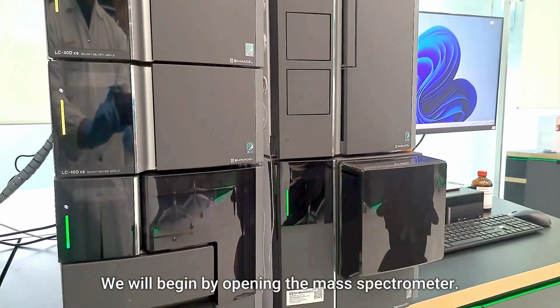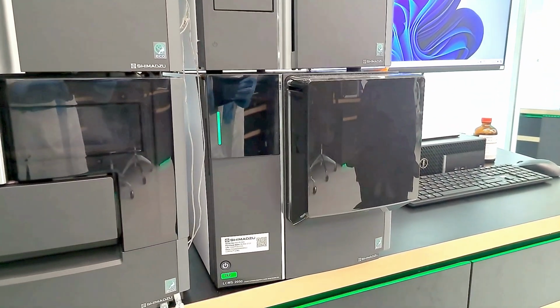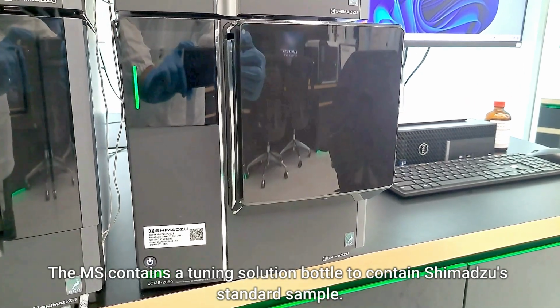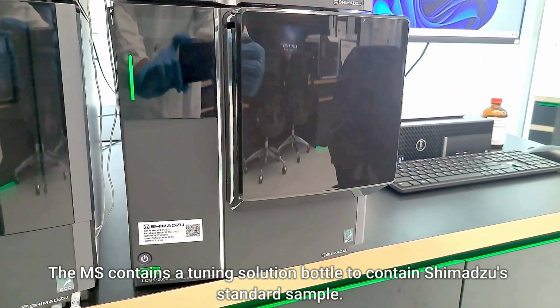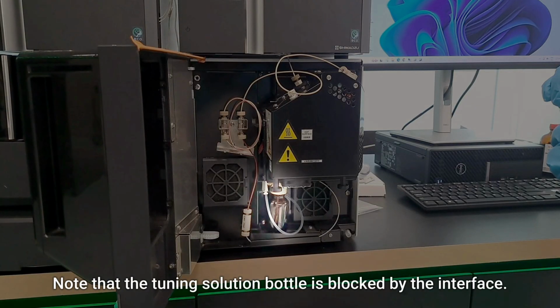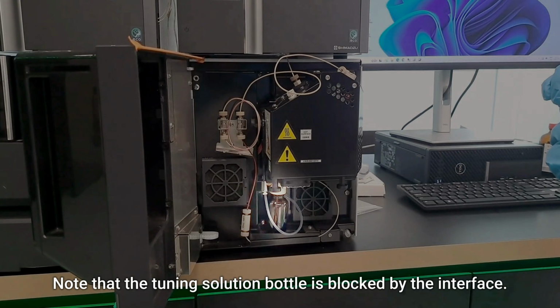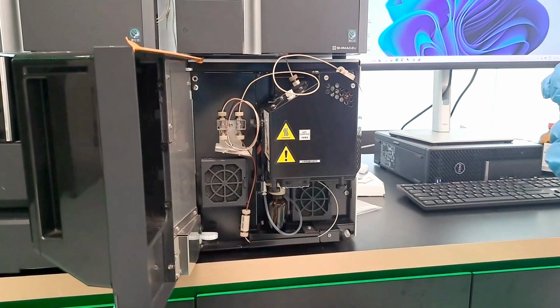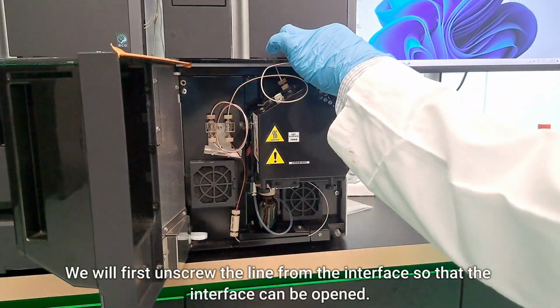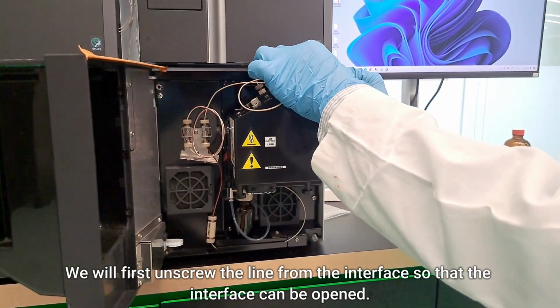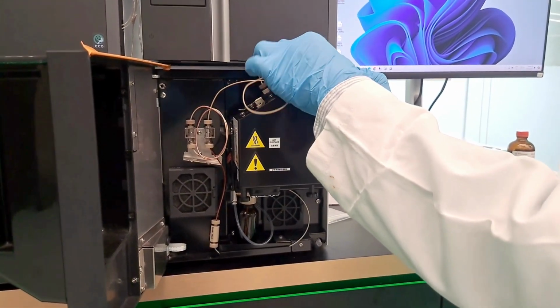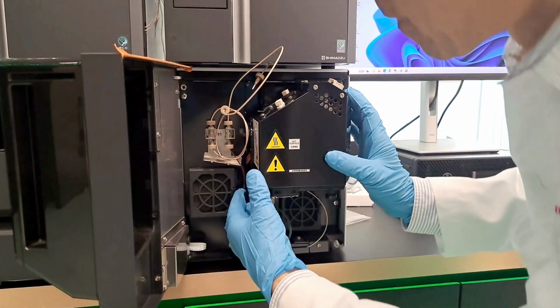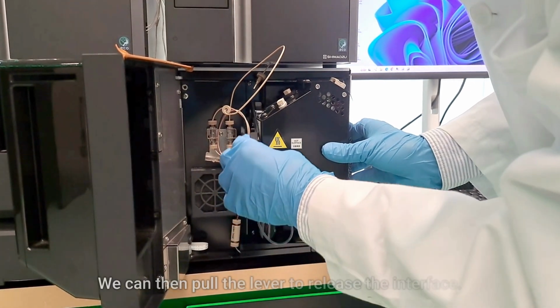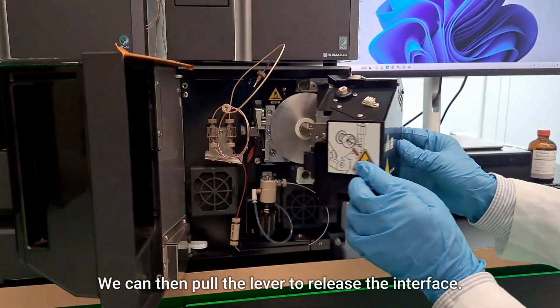We will begin by opening the mass spectrometer. The MS contains a tuning solution bottle to contain Shimadzu's standard sample. Note that the tuning solution bottle is blocked by the interface. We will first unscrew the line from the interface so that the interface can be opened. We can then pull the lever to release the interface.